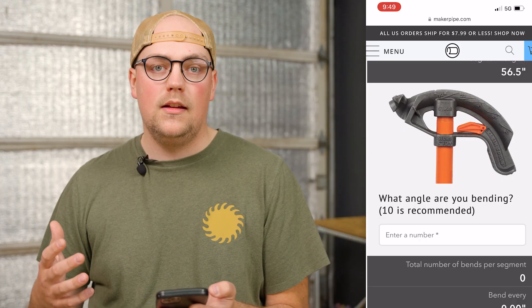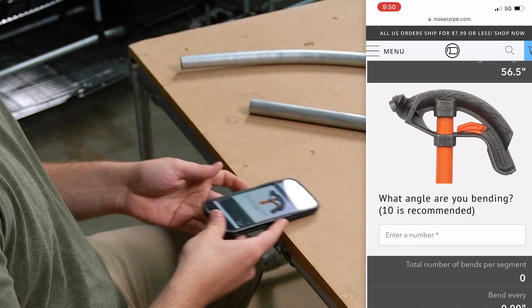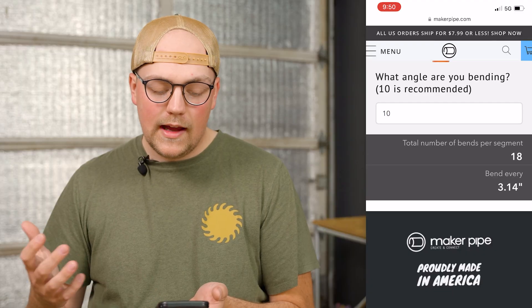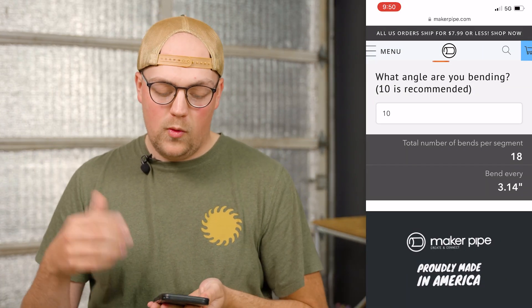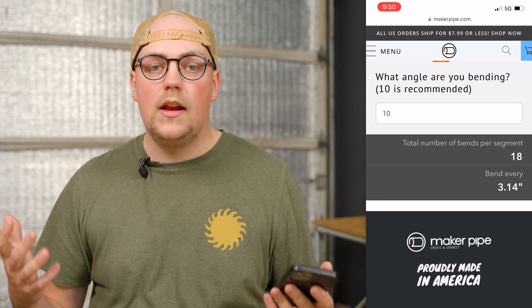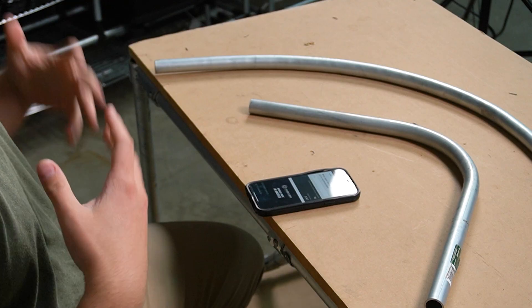The last thing we need to know is what angle we want to bend. I recommend 10 degrees — it's nice and simple, already engraved on the bender head, and gives a nice curvature. If you go higher, like 20 degrees, you'll get more of a flat edge on each bend and it may not look as circular. Once we enter 10 degrees, the calculator tells us the total number of bends per segment: 18 bends. And the spacing: every 3.14 inches — about three and an eighth inches — I'll bend 10 degrees for a total of 18 bends. That's all we need to know.